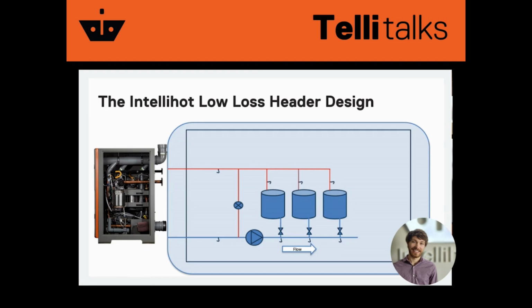Now, what happens when flow starts to increase is that a small amount of flow starts to go through my bypass line. This is why the bypass line exists inside our units. At a certain point, the pump pushing flow rate through the heat exchangers is no longer the path of least resistance. So water starts to flow up through the bypass. This is why we have manifold inlet and manifold outlet temperature sensors. The temperature sensors are going to correct the outlet temperature for the small amount of flow rate that's bypassing through the bypass line.